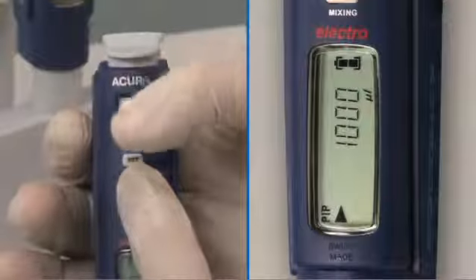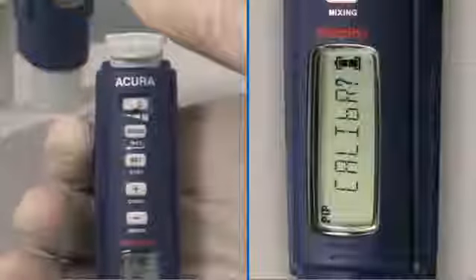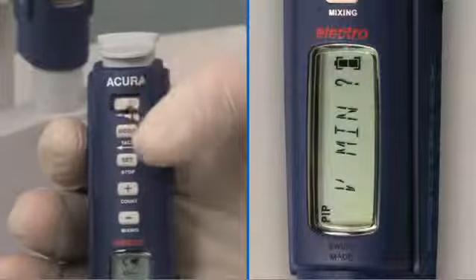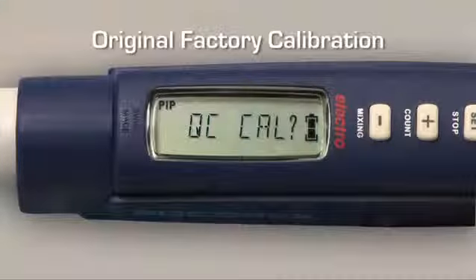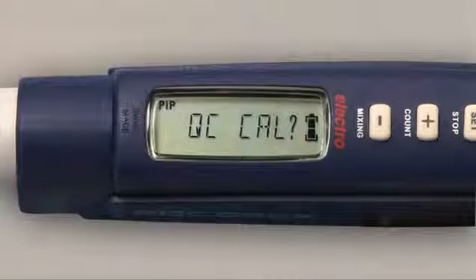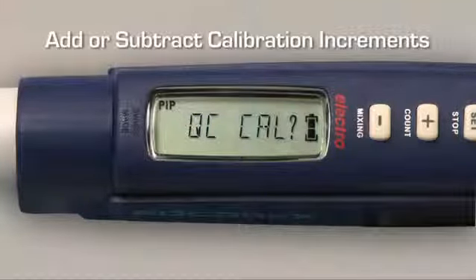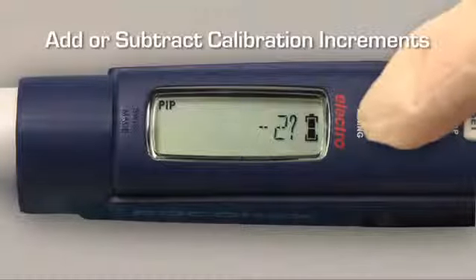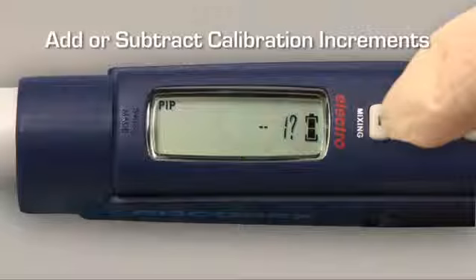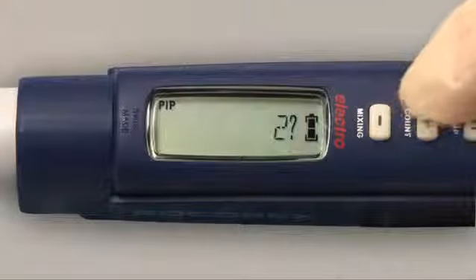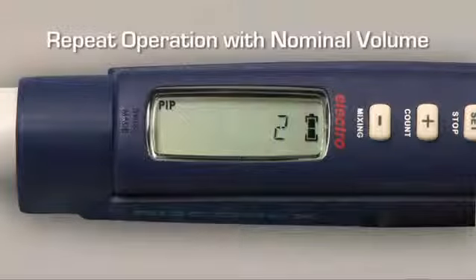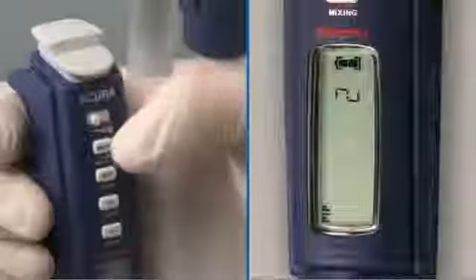To access the calibration menu, first press the plus button, then press simultaneously Mode. Select the calibration point, always starting with a small volume. In the calibration menu, QC-Cal is the original calibration value for a factory calibrated instrument. Other volumetric modules purchased as accessories will display 0 as the target calibration value. Calibration is performed by increasing or decreasing the calibration increments according to the values given in the operating instructions. To the calibration value indicated on the display, add or retrieve the number of calibration units. Repeat the operation with a nominal volume. When the calibration is completed, press the Mode key to return to the pipetting modes.